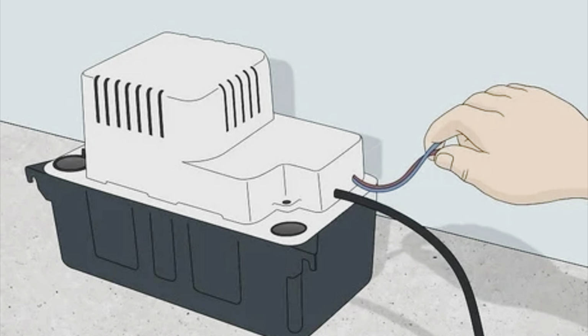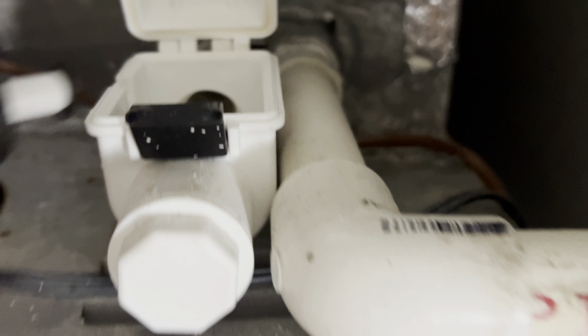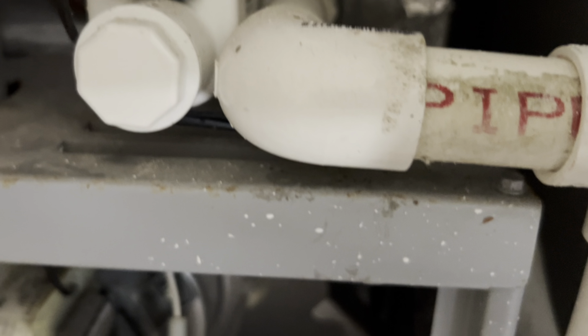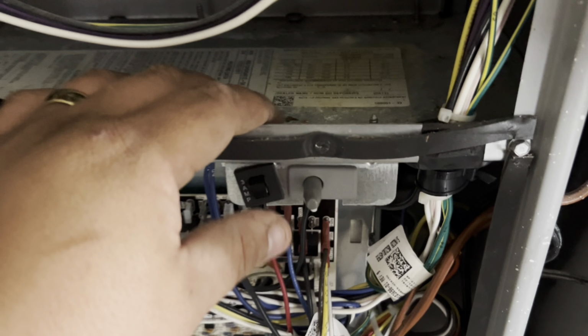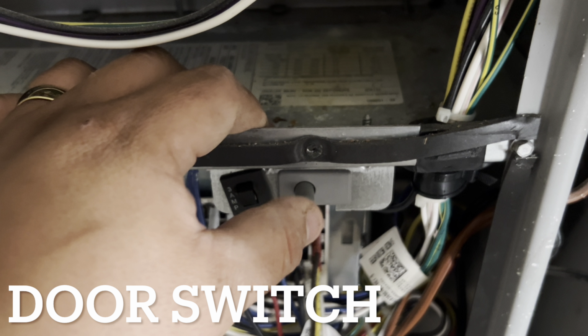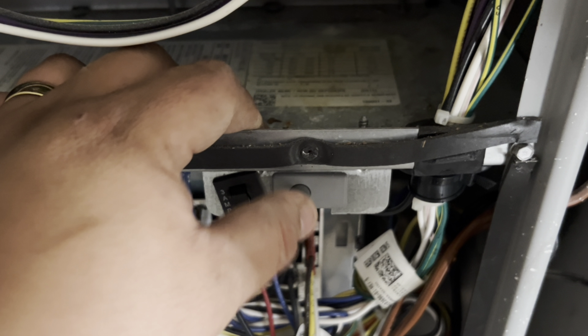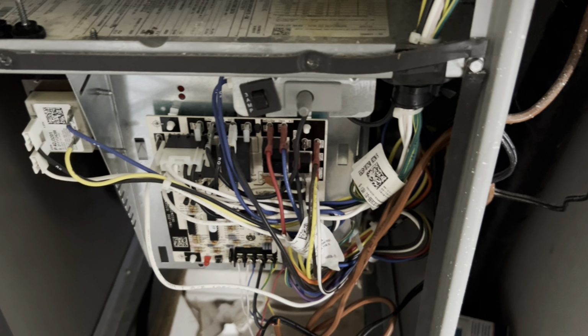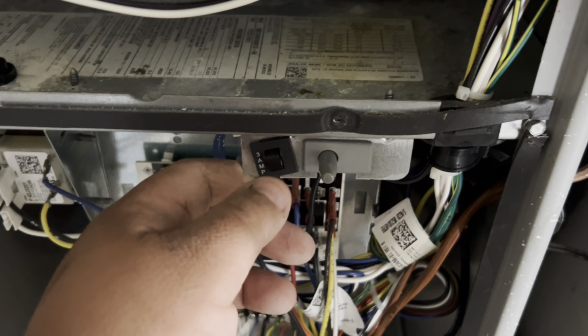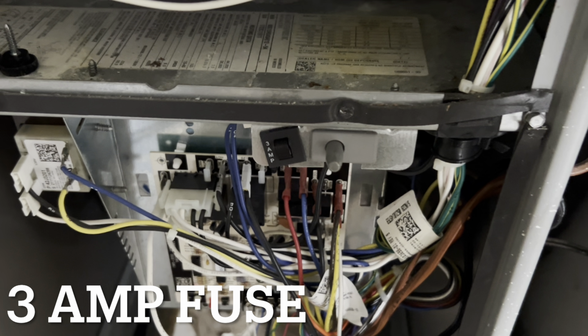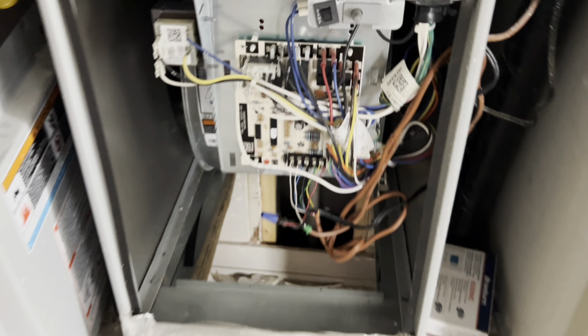Some units without a gravity drain will have this condensate pump that has a built-in float switch. If there is an issue with the drain, likely the drain will have to be cleared out using nitrogen or some sort of pressurized air. Moving on to the actual furnace, there is a door switch that prevents the unit from running if the front panel is missing. To the left of the door switch is a 3-amp fuse that will pop out in case there is a short on the low voltage.